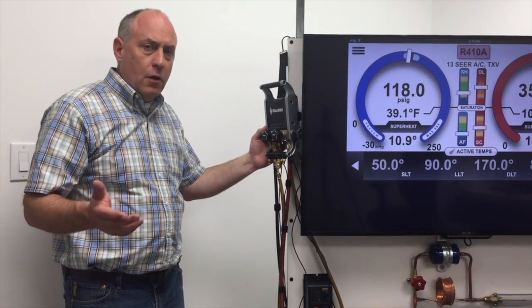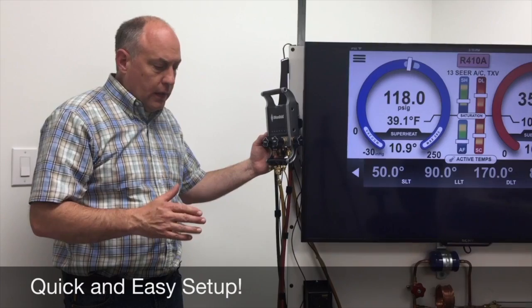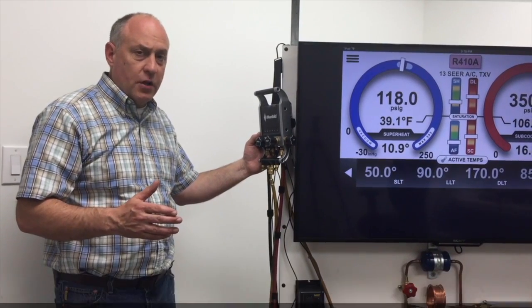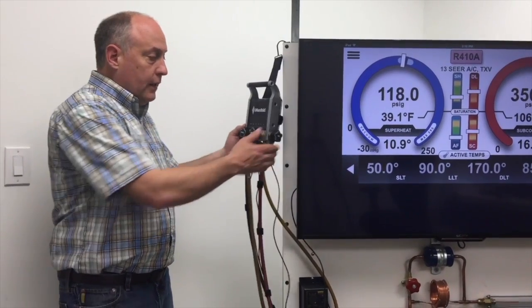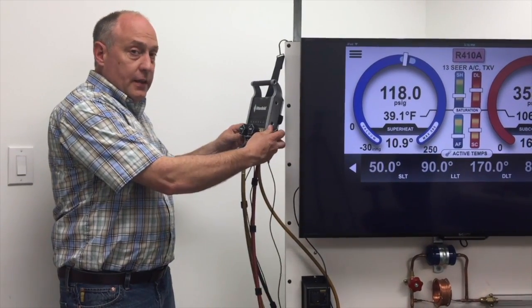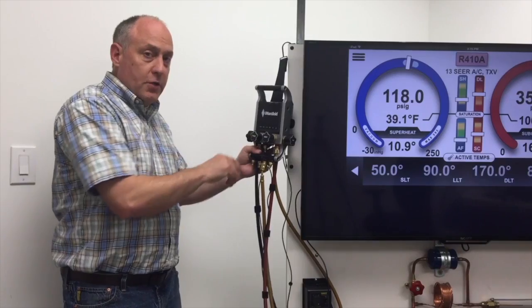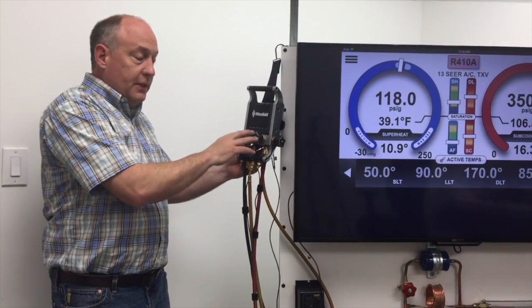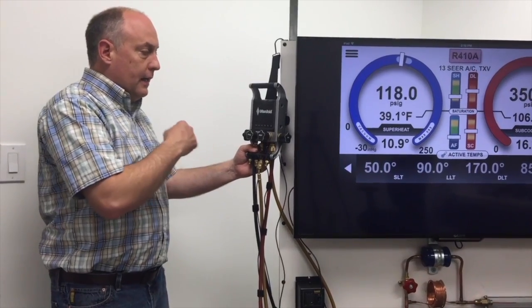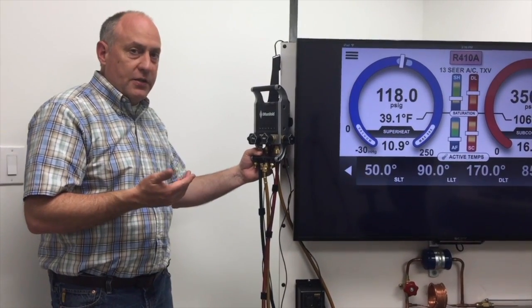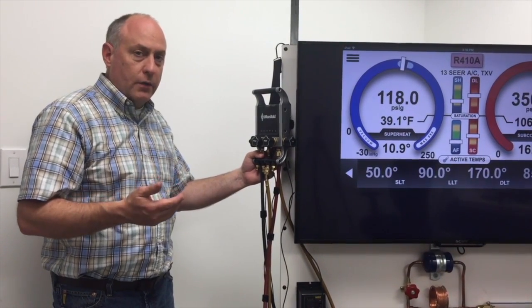So now that we have the low and high side connected, our liquid line and suction line temperature sensors on, the only other thing we need to do is turn on the Imanifold to get things going. Just like a standard manifold set, the gauge ports are all closed when we're measuring pressures. The only time you open these up is when you're adding or removing refrigerant. We're going to take you through the next commissioning process in another video and walk you through the process.